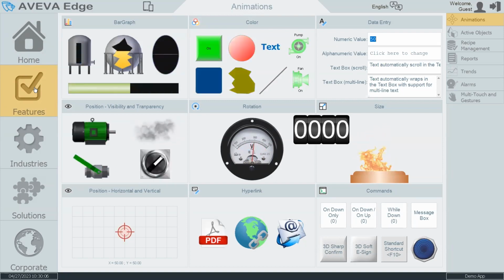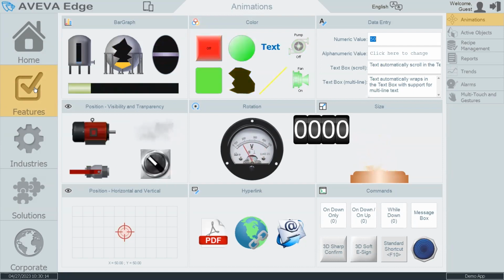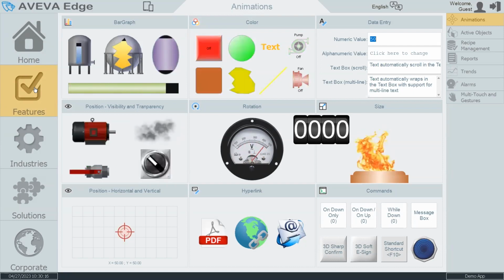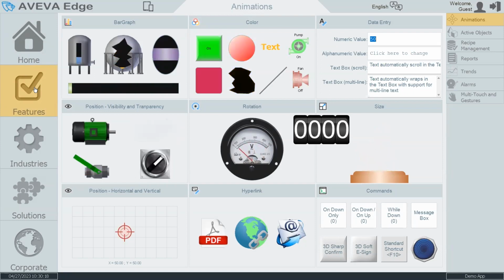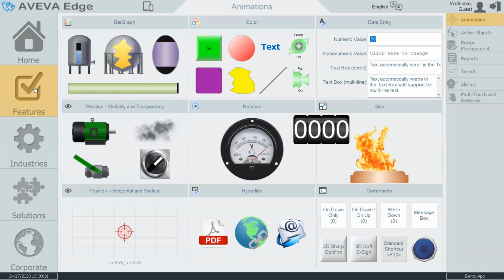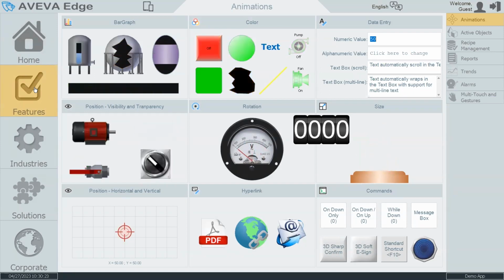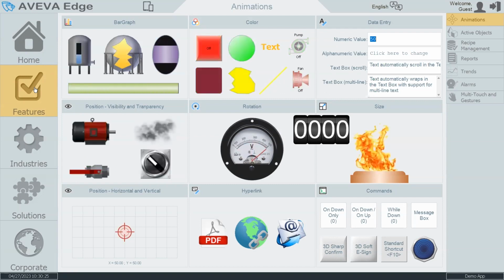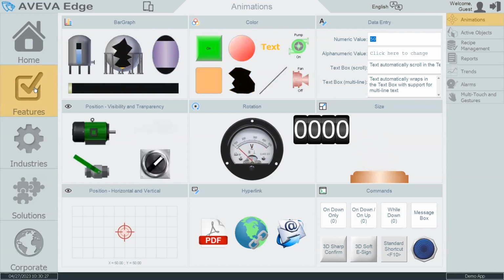The numeric and data entry fields are used, for instance, if you want to set an analog output value, so that something that's going from 4 to 20 milliamps in the background is controlled by 0 to 100%. So you can do scaling within AVEVA Edge or Indusoft.